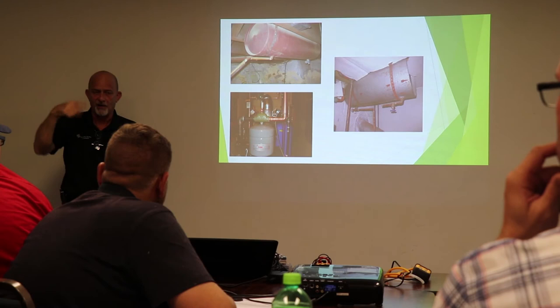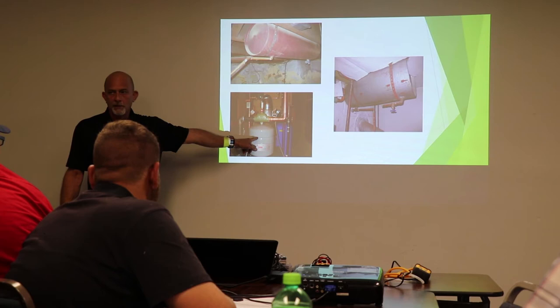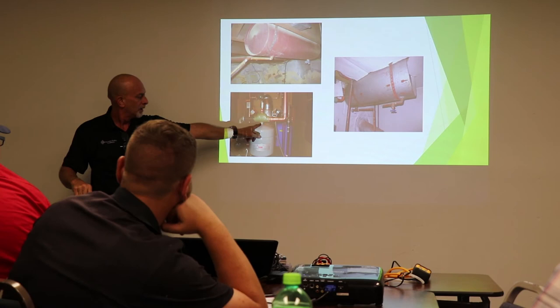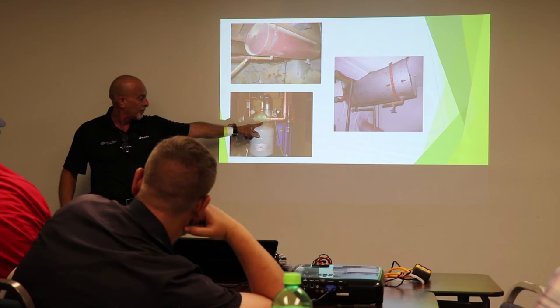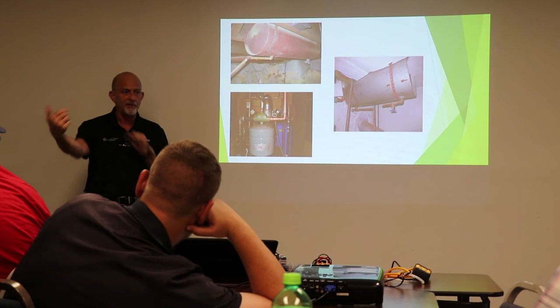These guys, if they're bad, you can change them on the fly if you want to get a little wet. Typically, when I ever put one in new, I put a valve in here. That way, if I ever had a bad tank, shut my valve off, spin it off, spin my new one on, open my valve back up, I'm done.